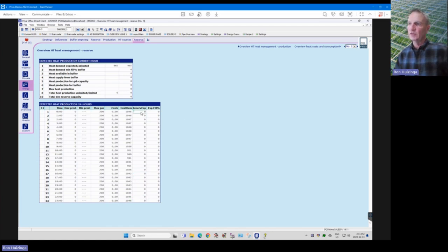And the next morning it'll say, oh, it's dropping down to below 60%, and I need 60% because in the morning it's going to be cold. So now it'll start running the boiler, say at 3 in the morning, to keep that buffer tank at 60% full of heat till it comes along to CO2, and then it'll start running again for CO2 and reserve capacity to make sure there's enough heat in the tank.